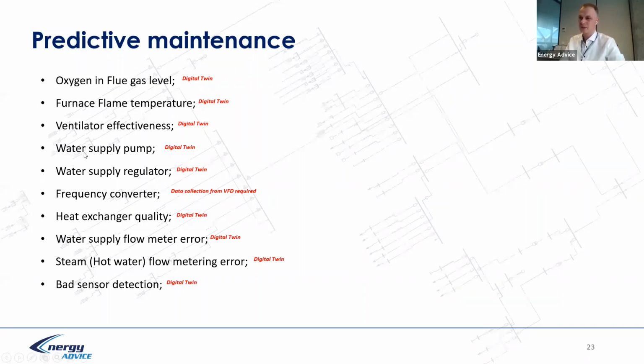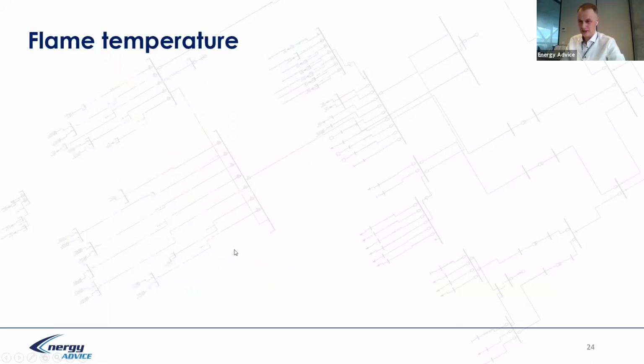Ventilator effectiveness, water supply pump effectiveness, water supply regulator performance, frequency converter performance. In fact, we need to collect data from the VFD. Heat exchanger quality, water supply flow meter error. Okay, metering error. We should understand what the metering error is, because flow meters also could make errors. Steam flow metering error and bad sensor detection in general. So all these things could be done through digital twin and would help us to understand boiler performance.